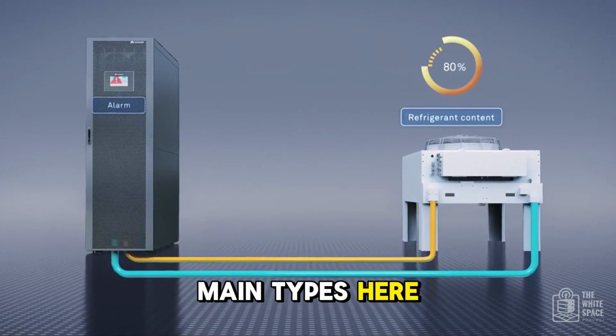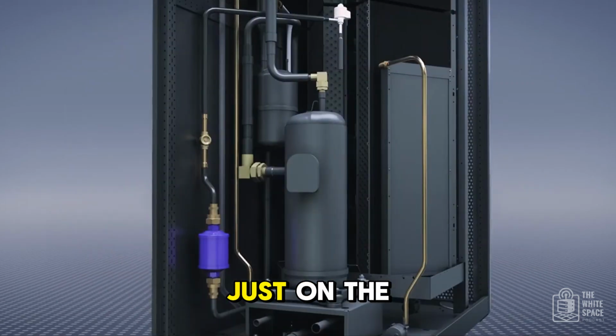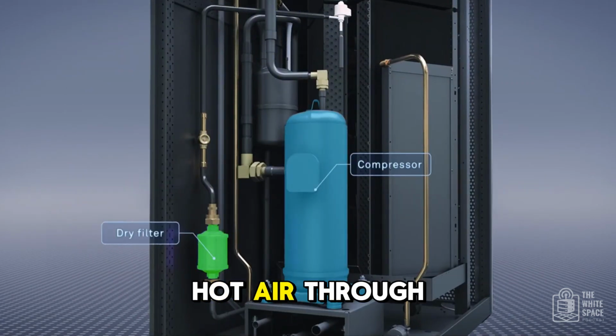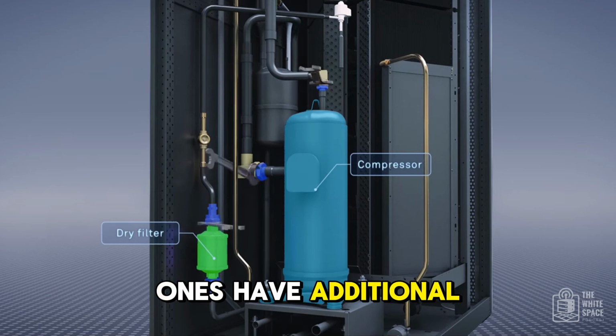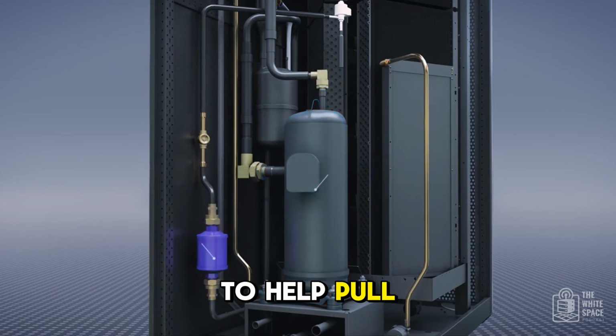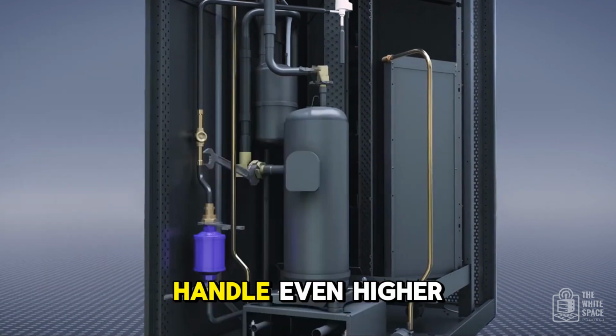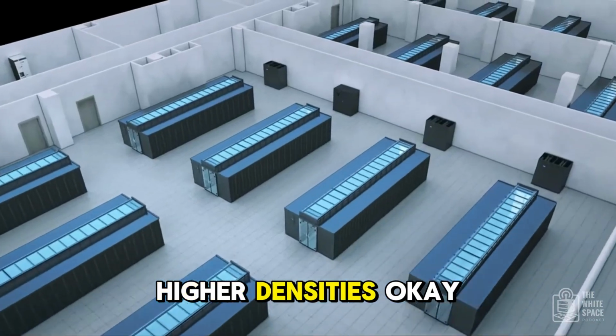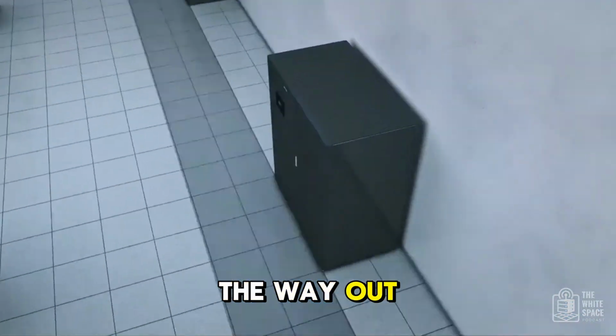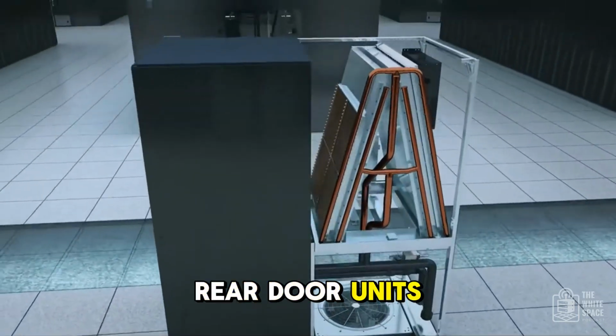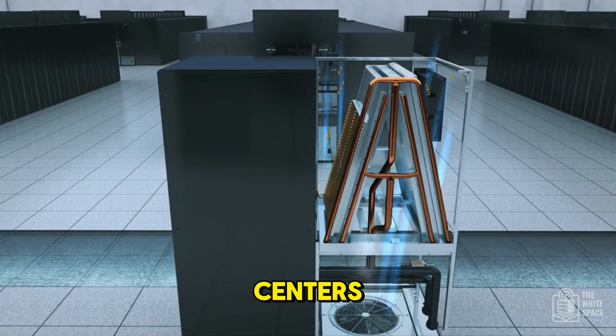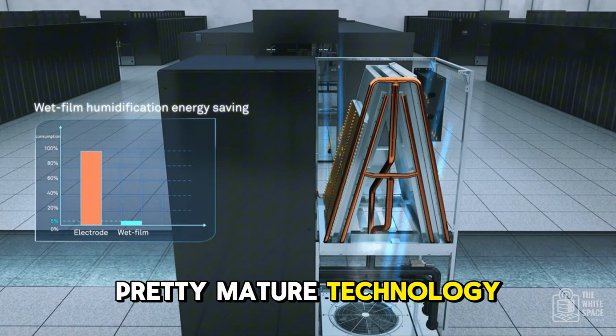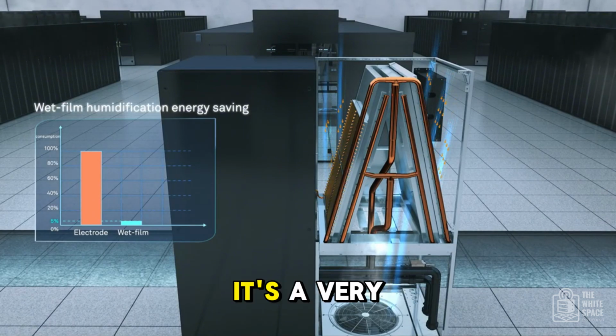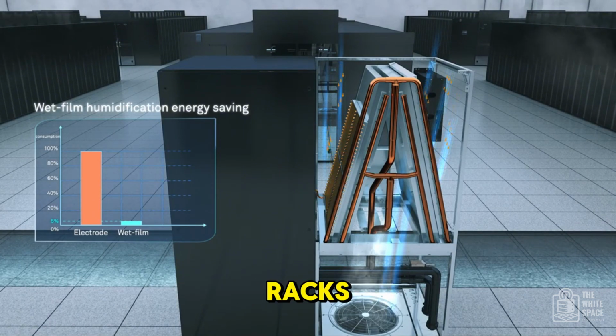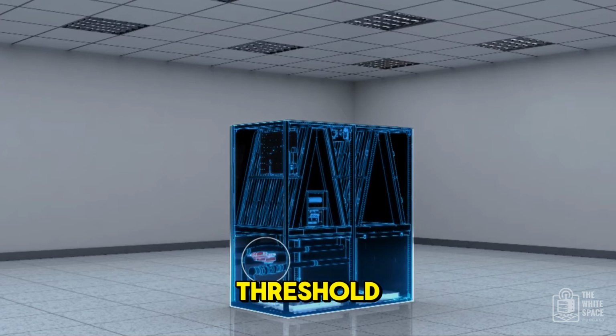There are two main types here, too. Passive ones rely just on the server's own fans to push the hot air through the coils. Active ones have additional fans built into the door itself to help pull more air through. This lets them handle even higher heat loads, higher densities. Okay, so it catches the heat on the way out. What makes these rear door units attractive for enterprise data centers? Well, it's a pretty mature technology now, quite well understood. It's a very solid solution for racks generating more than that 20 kilowatt threshold we mentioned.